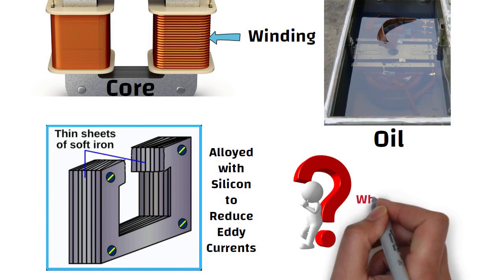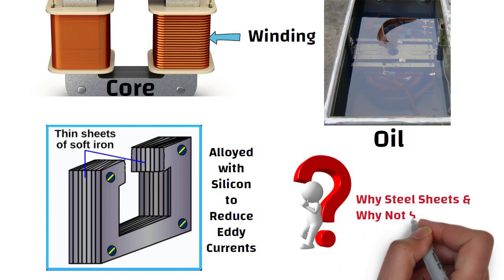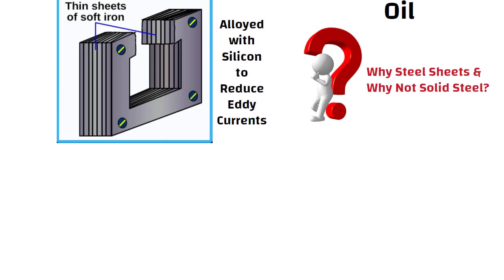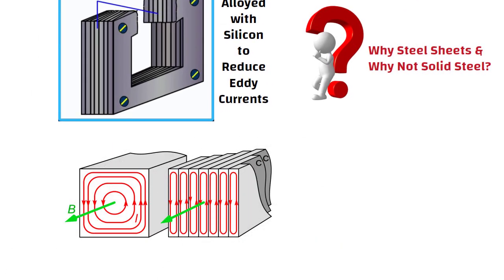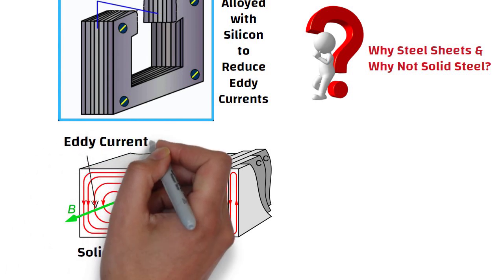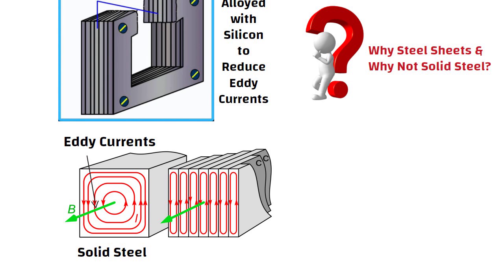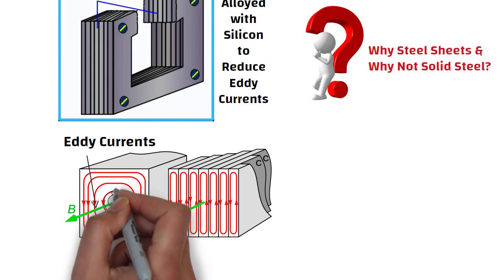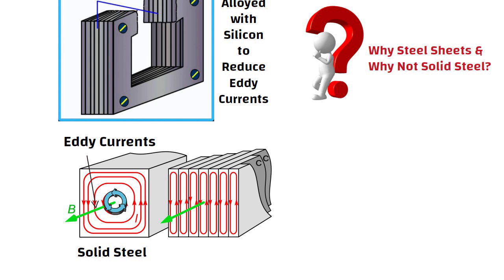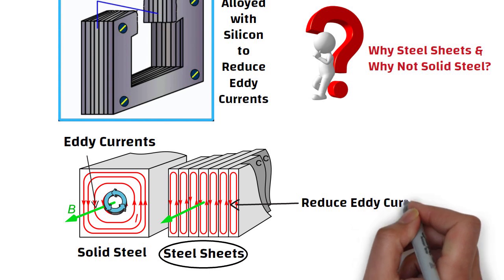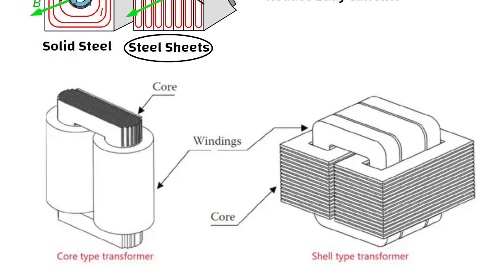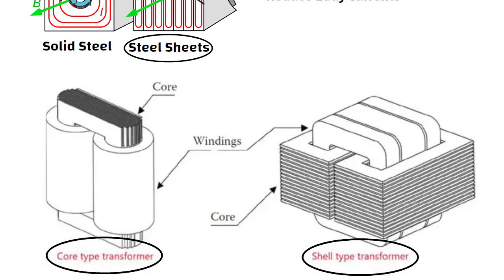Here is the question: why is a core made up of steel sheets and not a solid steel? You can see in this picture, it is because if we use solid steel, then it creates eddy currents in it, which oppose the main current flow. Eddy currents flow in closed loops within conductors. So when we use thin sheets of steel, we can reduce the eddy currents. There are two types of core constructions: core type and shell type. You can see them in these pictures.